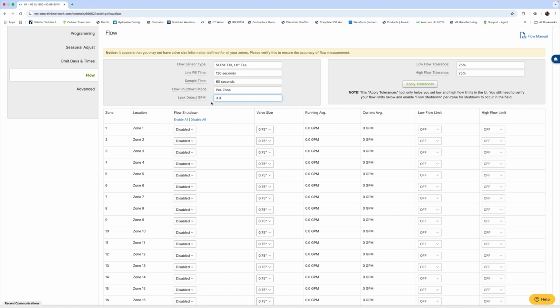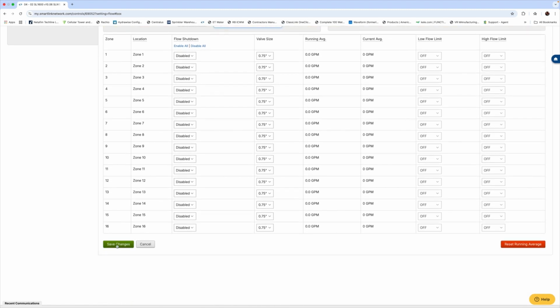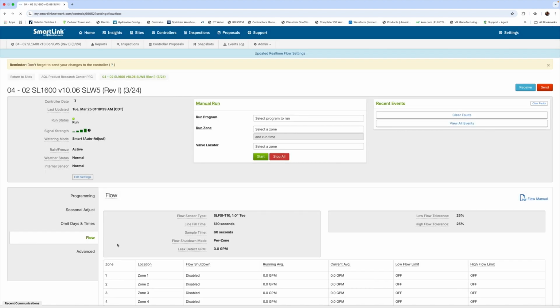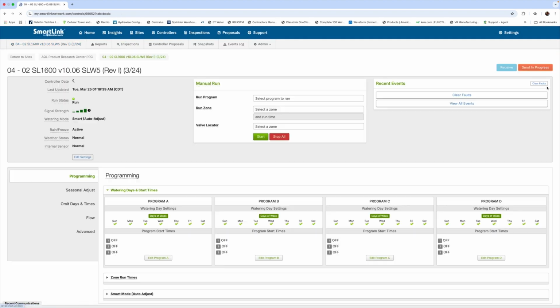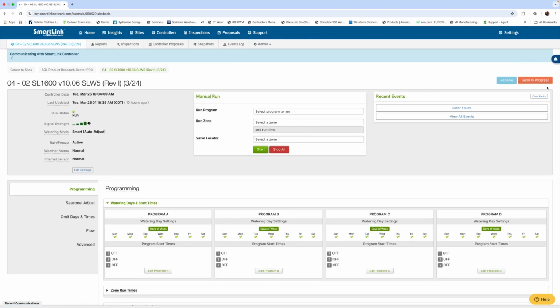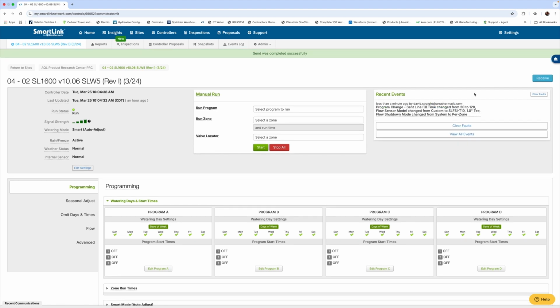And when you're all set with your programming, we're going to save those changes down here at the bottom. And then we're going to be sure to push this information to our panel on site. So I'm going to go ahead and click the send button. And as you can see, we're communicating to the SmartLink controller from SmartLink. And we want this instruction to be confirmed. So we're going to stand by and wait for the green instruction completed banner to confirm our operation has been successfully installed. Okay, great. As you can see, the send was completed successfully.